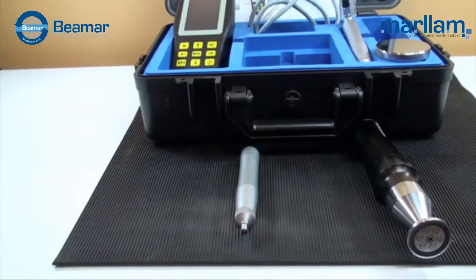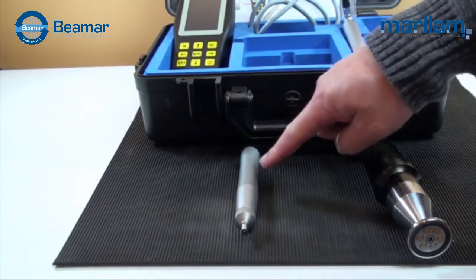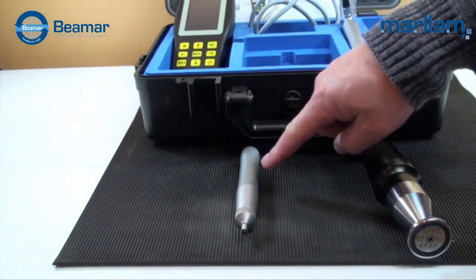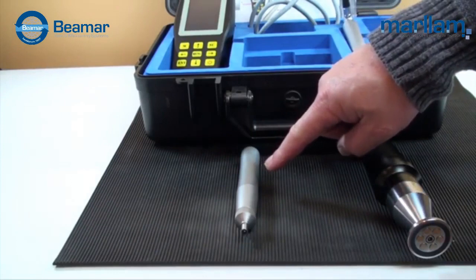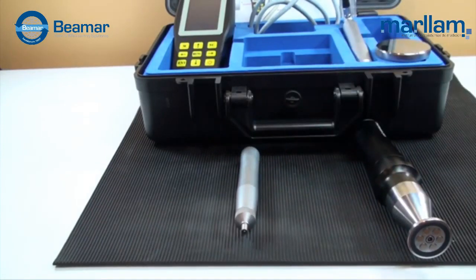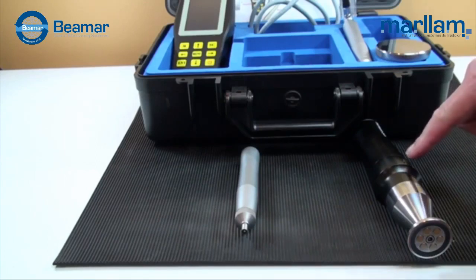There are 5 types of standard manual ultrasonic probes. They are generally determined by the load to be applied for activation. They include 1 kilogram, 2 kilogram, 5 and 10 kilogram. There is also a long nose 1 and 2 kilogram manual probe to get into tight places. The correct load to be applied will be determined by the surface roughness of the metal to be tested. Motorized probes are also available for very thin work such as platings and coatings.